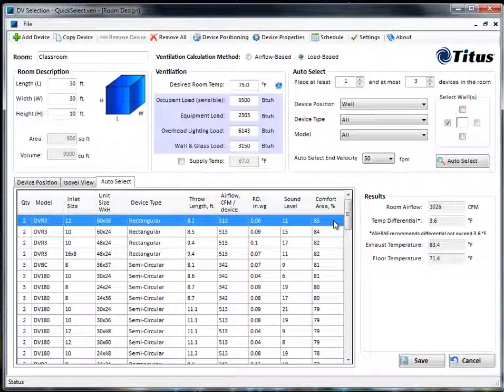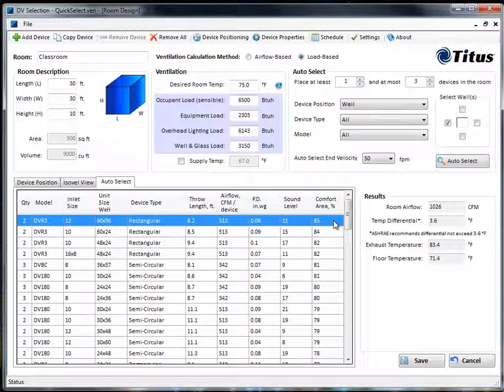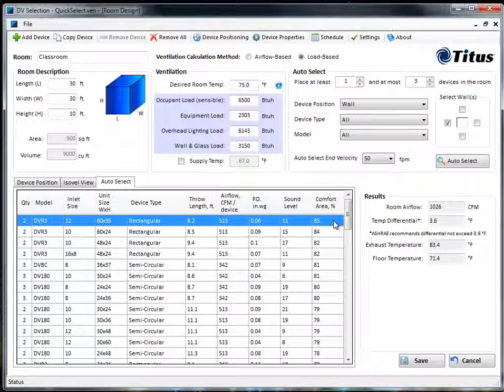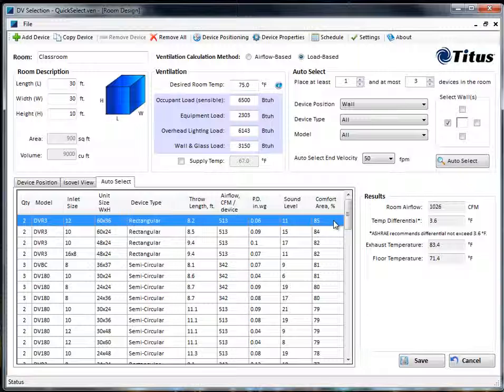If you recall from the 'What is Displacement Ventilation' podcast, because your diffusers are in the occupied zone there's an area around the diffuser called the adjacent zone where you should not place occupants. This area is where the airflow is 50 feet per minute or greater. The percent comfort area is the percent of the room that is outside of that adjacent zone — in this case it is 85%, the one below it 84%, and so on.